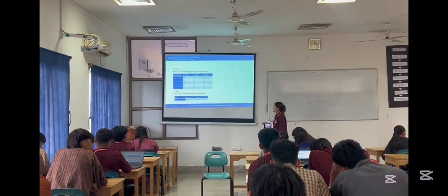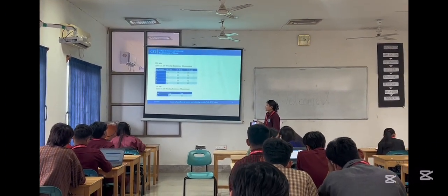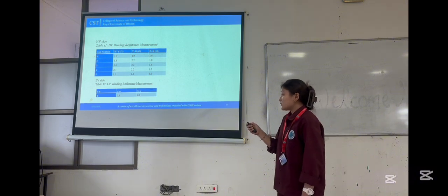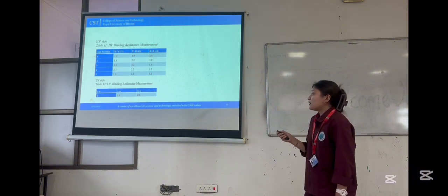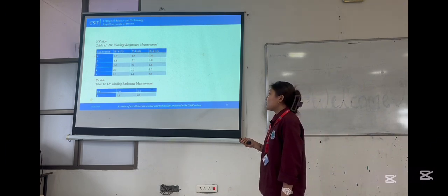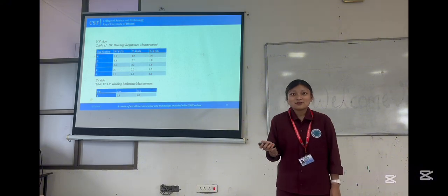To conclude this test report, since the results all conform, it means that the winding resistance test is good, so the test will pass. Whereas in the LV winding resistance test, since the Rn, Yn, Bn are balanced with each other, the test is good.